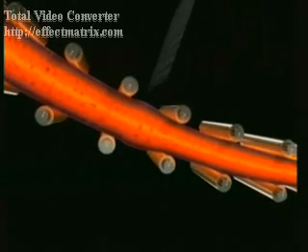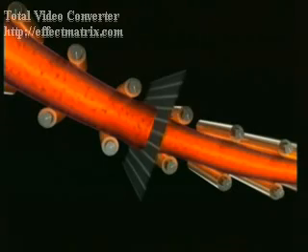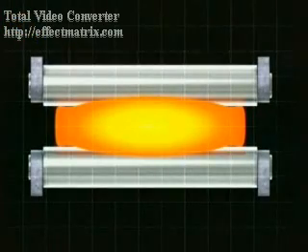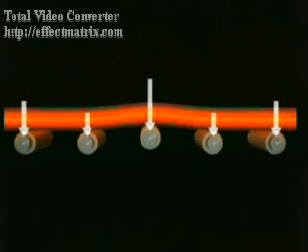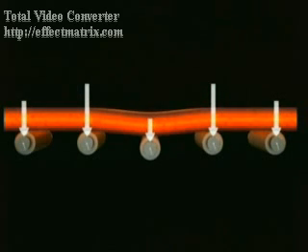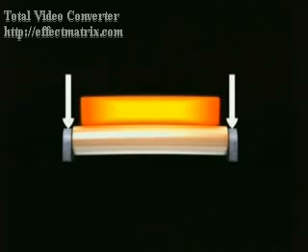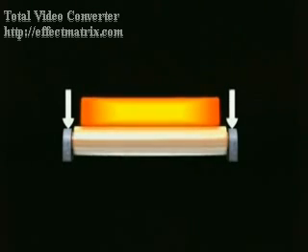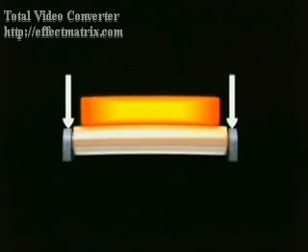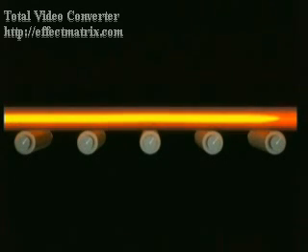On the one hand, if a roller is mounted too high, it will get overloaded. On the other hand, if a roller is mounted too low, the rollers next to it will get overloaded. A bent roller can cause large variations in the load distribution. This can give overload to both the roller as well as to the bearings. All these types of misalignments in the roll line geometry can have major influence on the internal quality of the steel, since inclusions can be created in the slab.